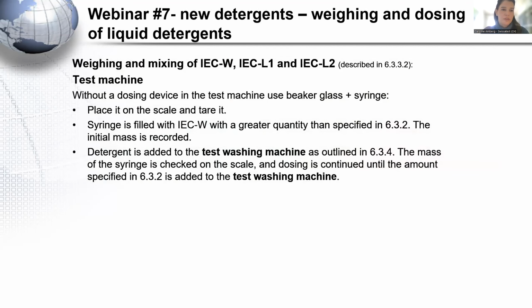Okay, then for the test machines, we are relatively happy in the round-robin test that for almost all test machines, we have a good solution: we can take out a dosing device and place it on the scale, except for China, where this is not possible. There we have to weigh and dose the detergent via a beaker glass and a syringe. This is the alternative when you cannot take out a detergent device or a detergent drawer directly and put it on the scale.